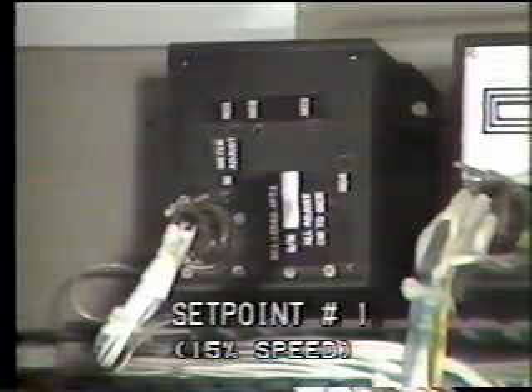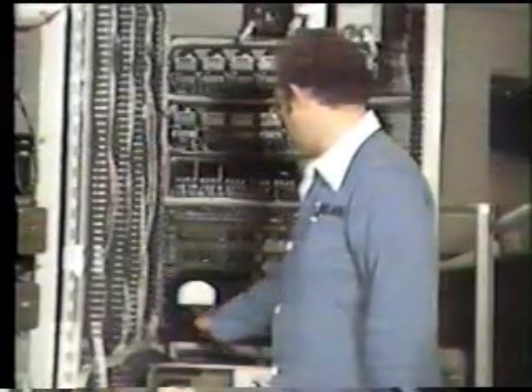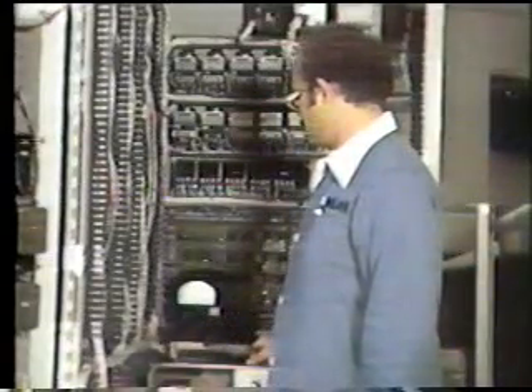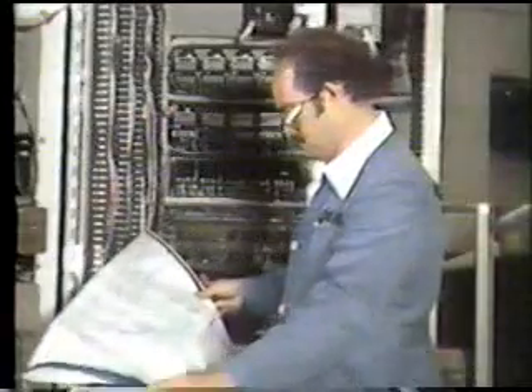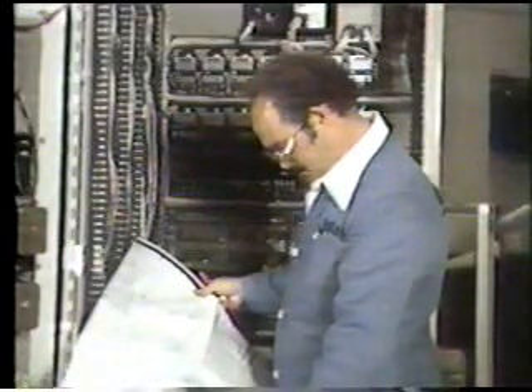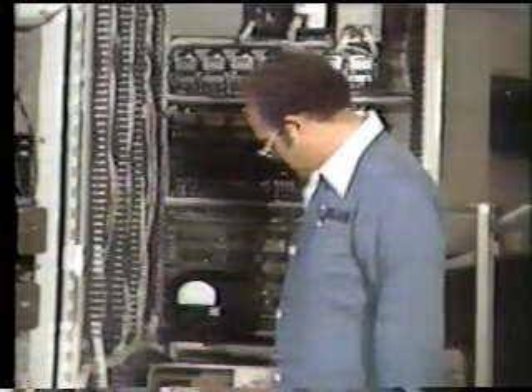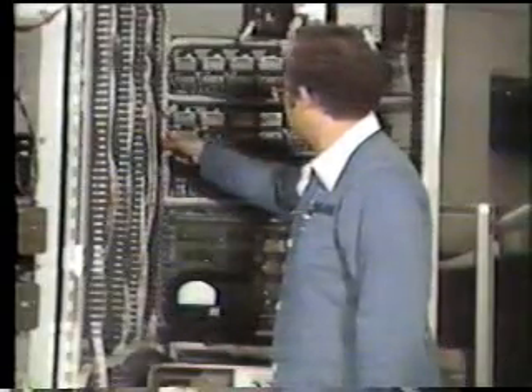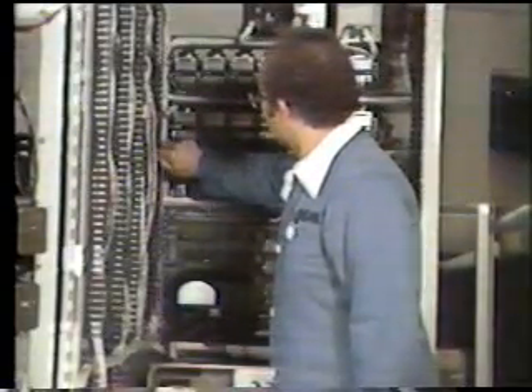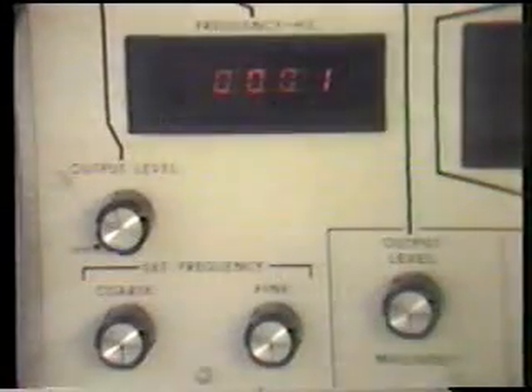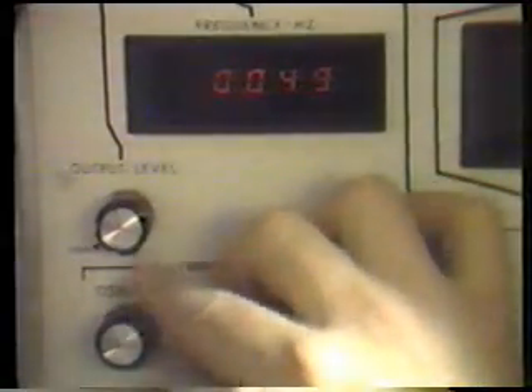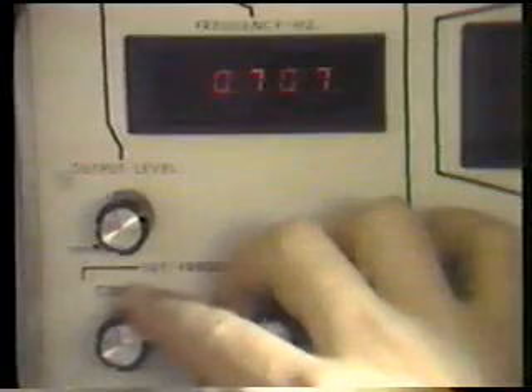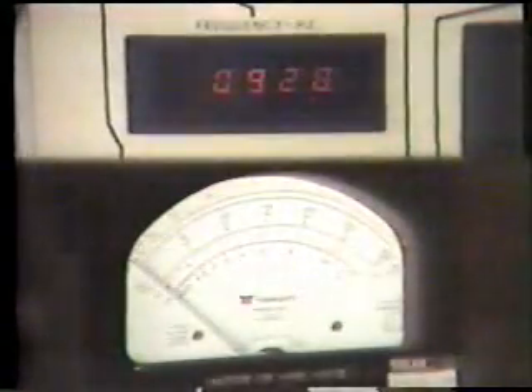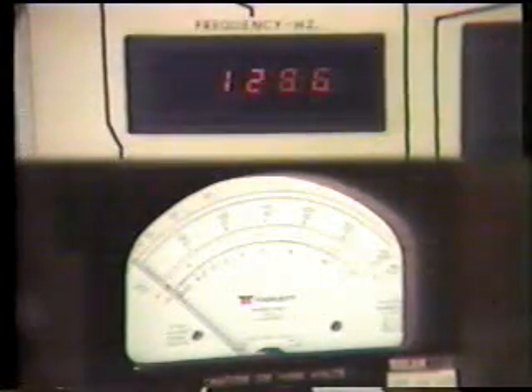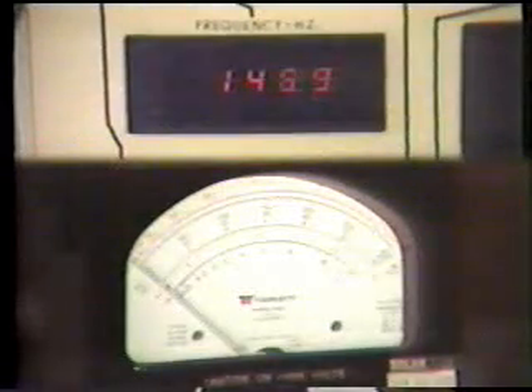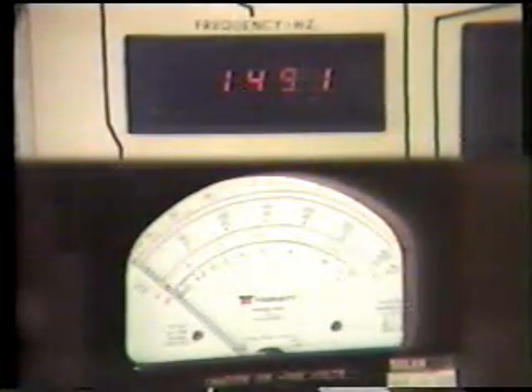Set the VOM to read DC volts on the 60-volt scale. Note the wire number for any set point can be obtained from a schematic and wire diagram. Then connect the test leads of the VOM to the 15% speed contact wire leads at the terminal strip in the control console. Next, adjust the output of the signal generator for the frequency equivalent of 15% speed plus or minus 30 Hertz. This is the transfer point of switch number 1. Be sure to check the electrical schematic to verify the set point frequencies. All sets may not use 15% speed.